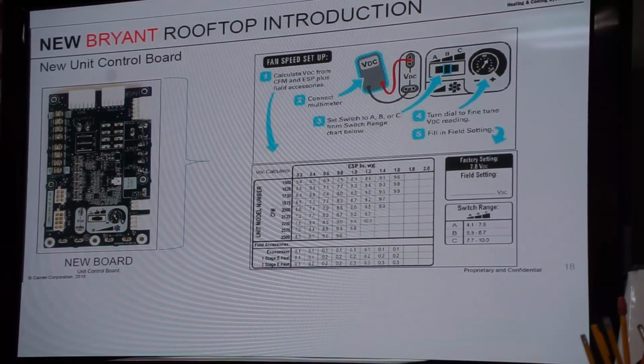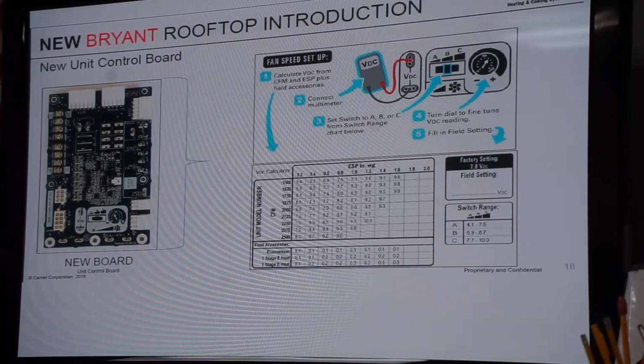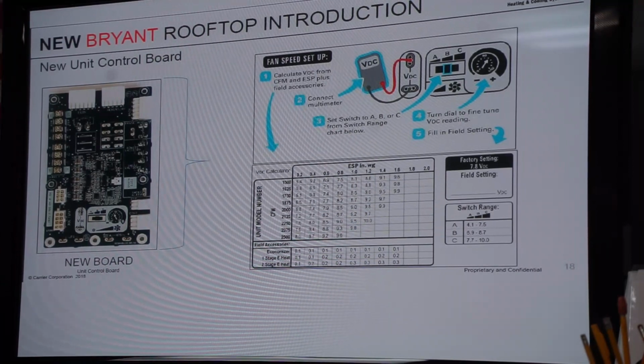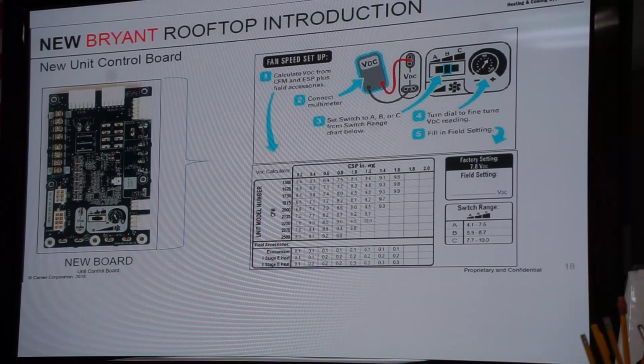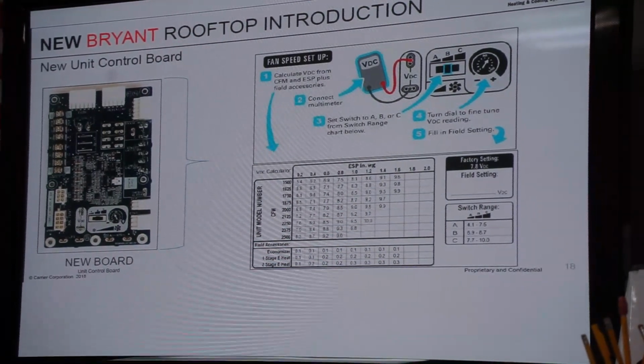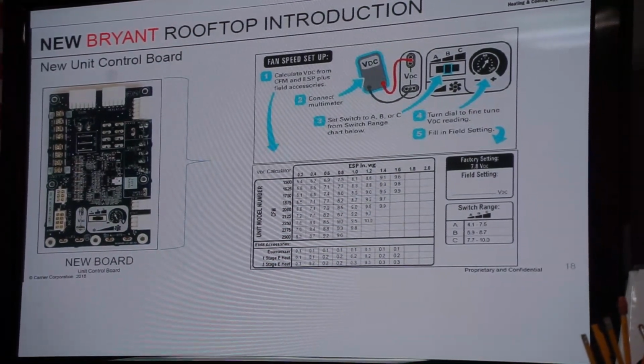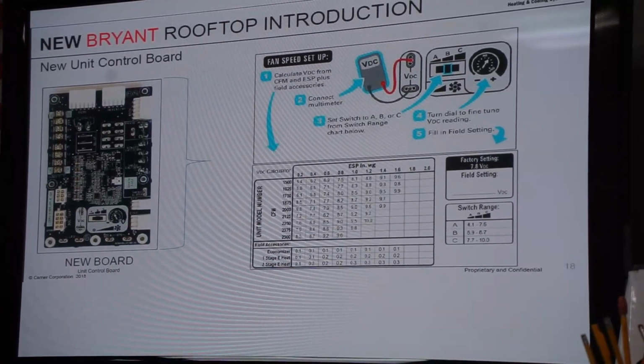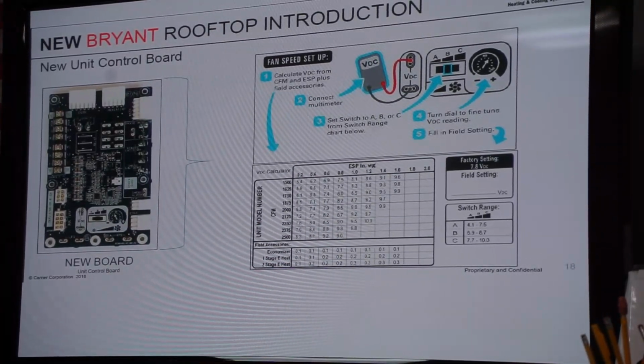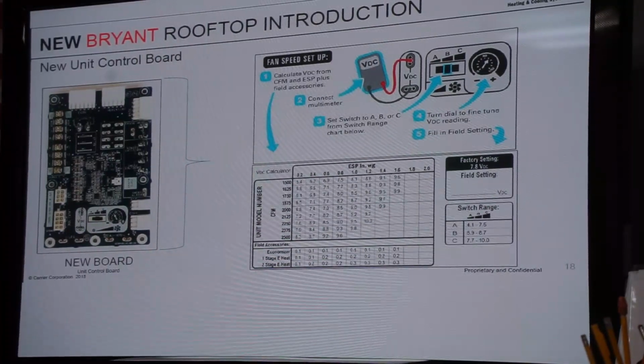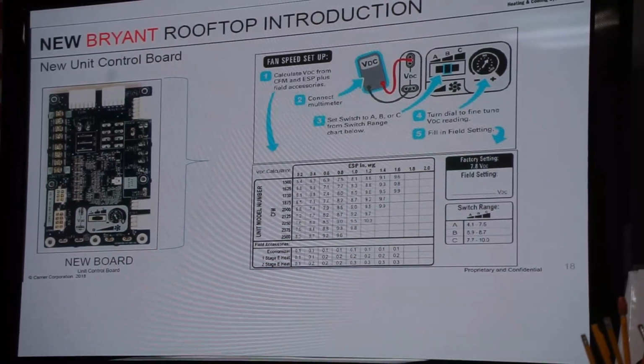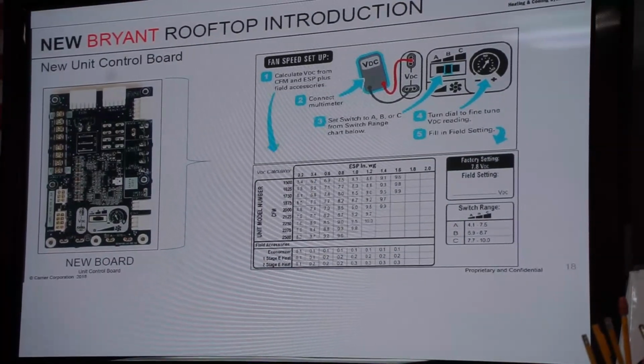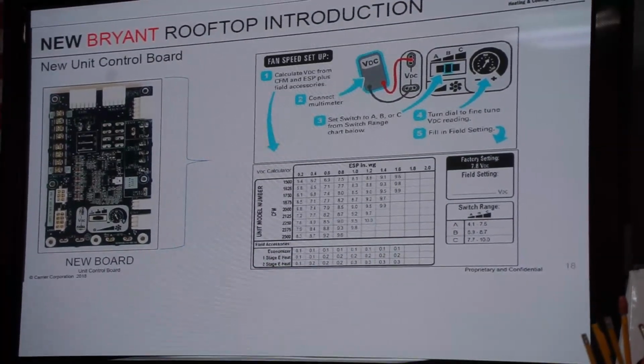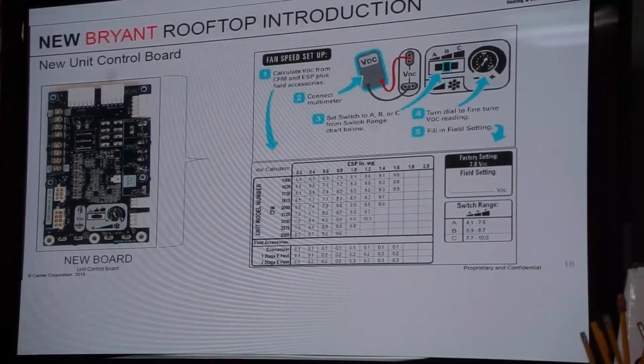Now, how many times did we adjust the fan sheave on a startup back in the day? Only when we had a problem, right? If we hit the go button and it cooled and heated the way we thought it should, we weren't rolling that sheave in or out. I want the same mentality: I'm going to ballpark it with this, but I don't know exactly what the external is, even if it's on the schedule. Remember that schedule we looked at? Everything was 1 inch on the ductwork. 1 inch external, 1 inch external.